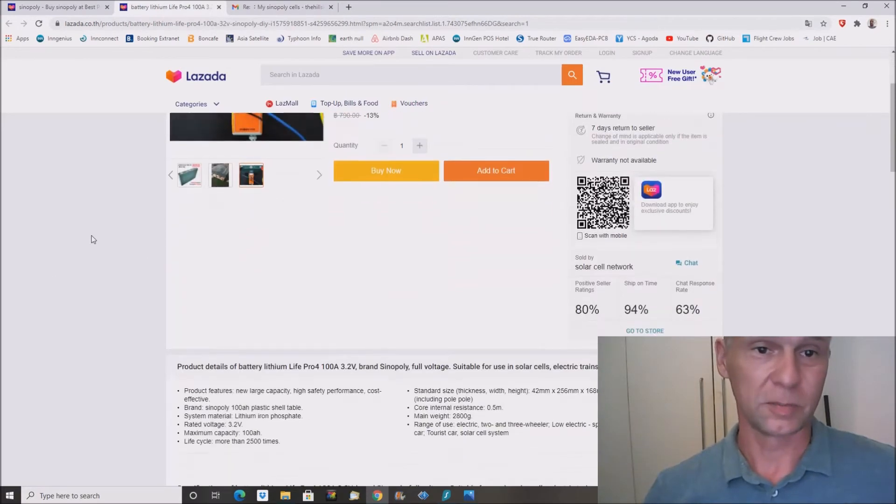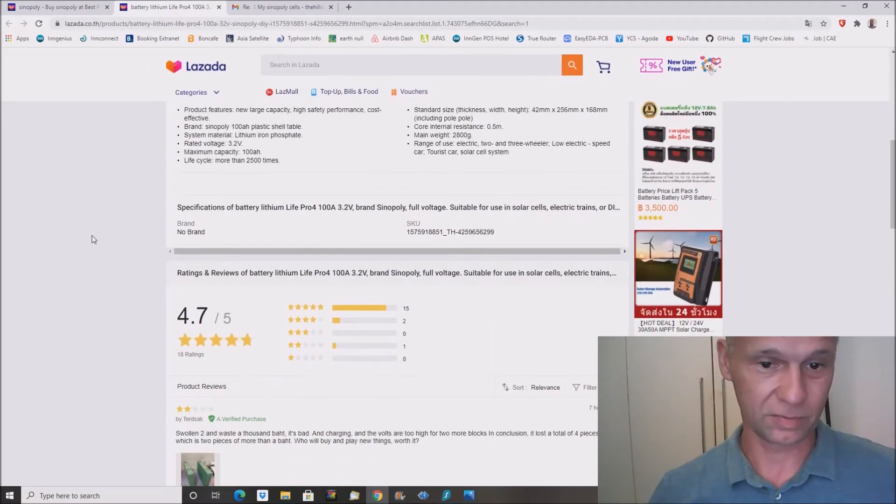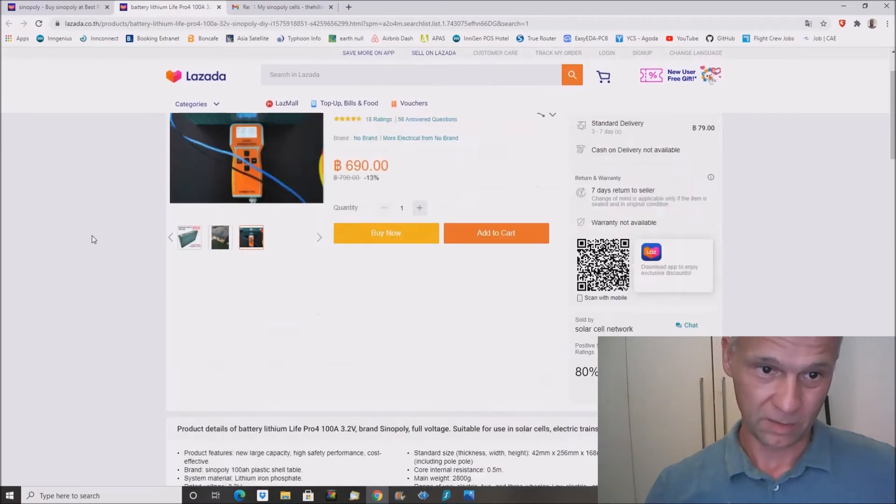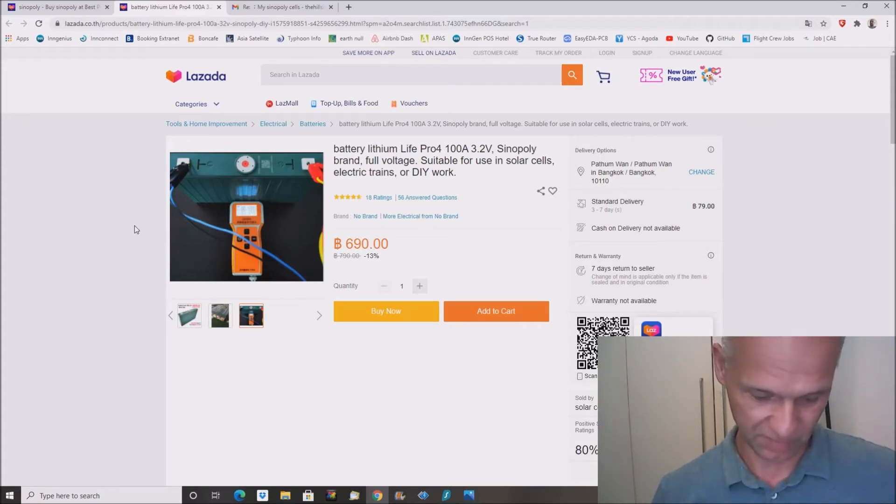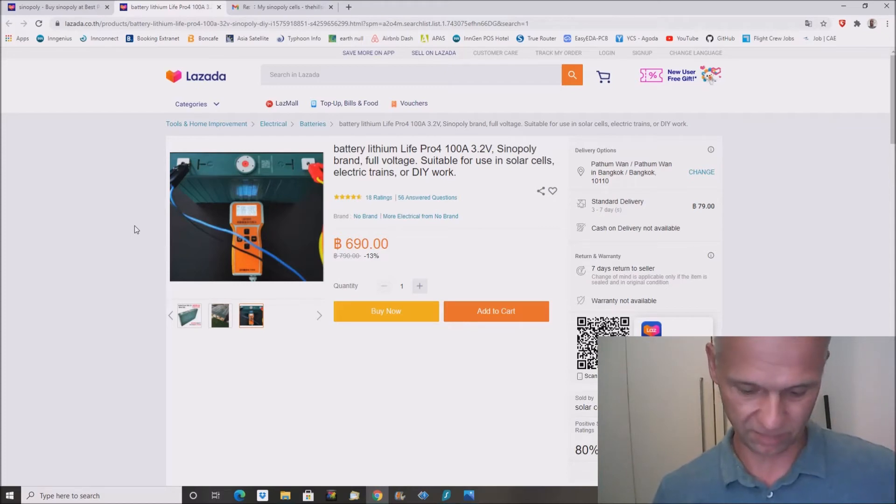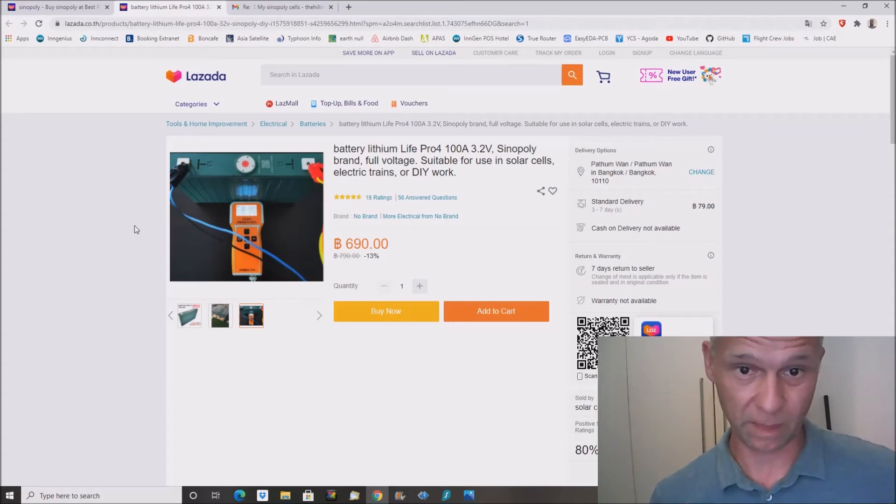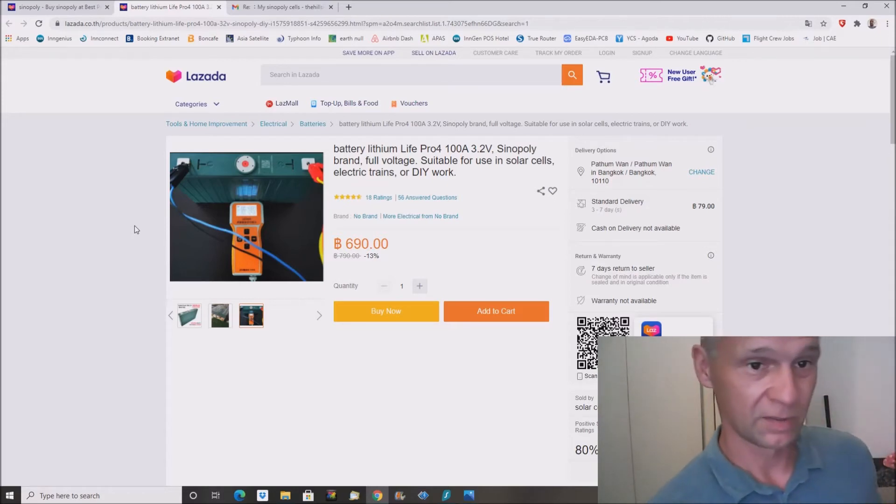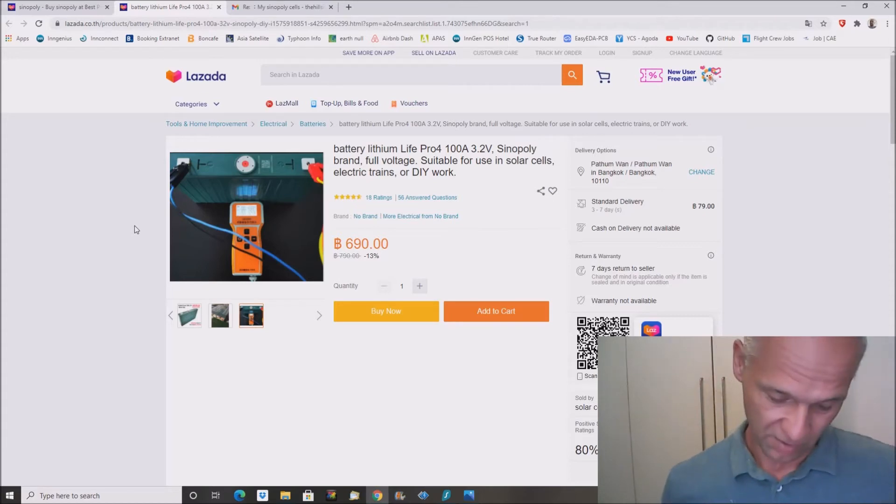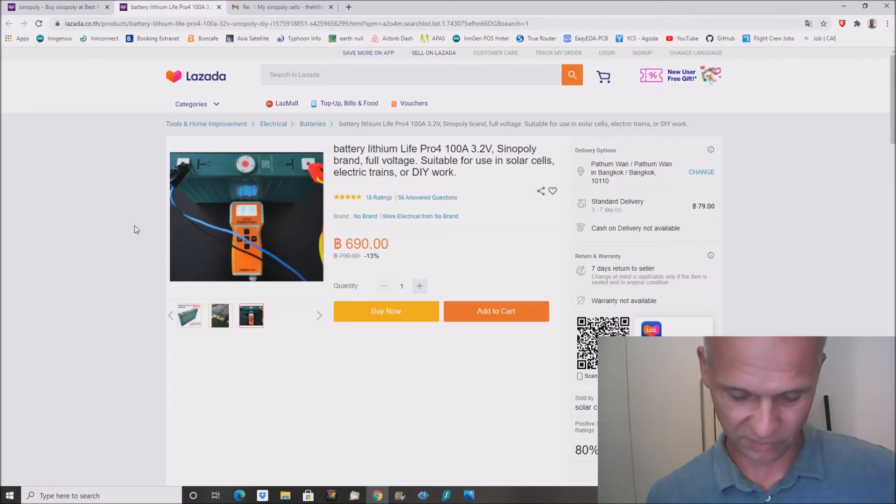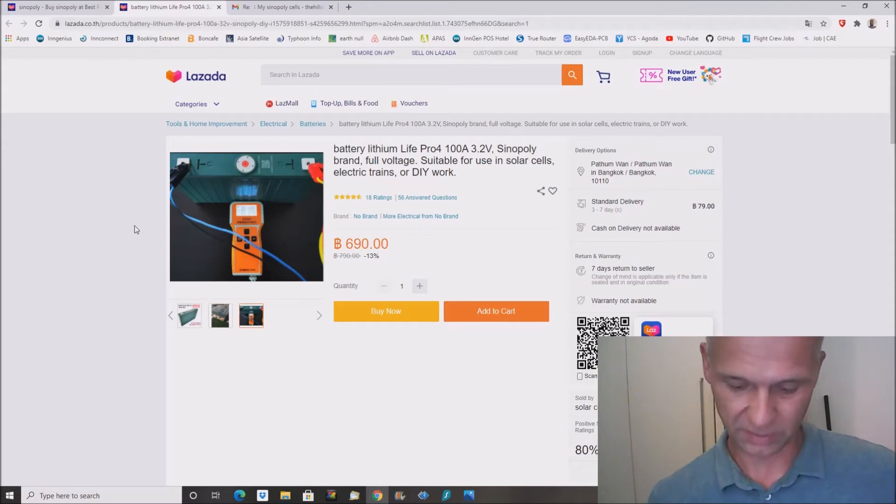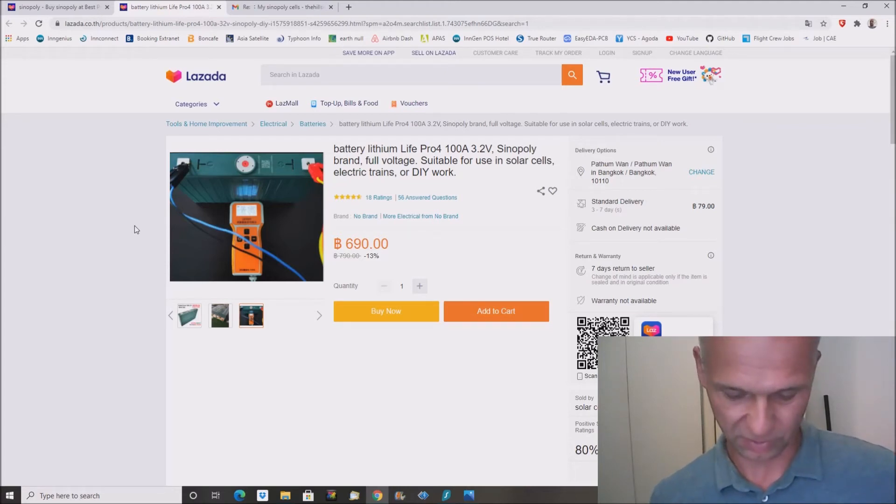So how much is that and why is that of interest? Well, 690 Baht for 100Ah, 690 Baht equals 23 US dollars. And just keep in mind, these are used cells. In my case, they degraded between 10 and 15%. So if I calculate a 15% degradation into this price, then one kilowatt hour from these cells costs 80 US dollars, so far below 100 US dollars per kilowatt hour.